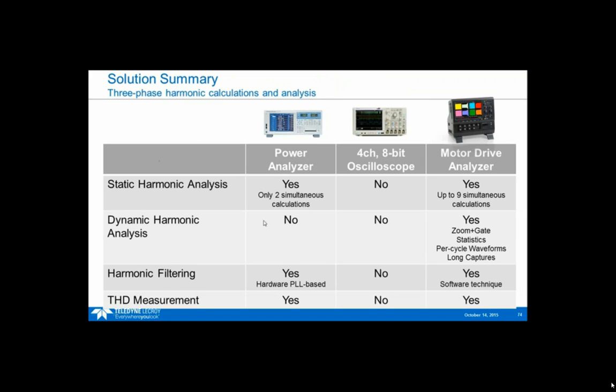So if we look at the solution summary, again, static and dynamic analysis is a recurring theme. Here with the harmonic filtering, the power analyzers do this as well, usually hardware PLL based, built into their FPGA, so they pre-process all the data. But it has a very limited operating frequency response rate, so it's really meant only for a static situation where the load, speed, and torque aren't changing very much, because the PLL might not capture all the changes in real time for all the harmonics. We use a software technique, a post-process technique, so no matter what the response rate of the system is, we'll capture and measure everything appropriately. There's a THD measurement for us, and there is also for most power analyzers. The exception is that for us, you can plot the value over time, which isn't true with the power analyzer.